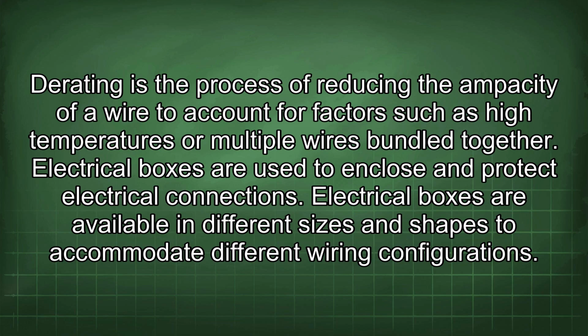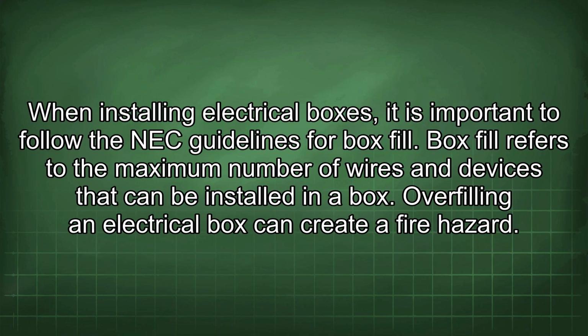Electrical boxes are available in different sizes and shapes to accommodate different wiring configurations. When installing electrical boxes, it is important to follow the NEC guidelines for box fill. Box fill refers to the maximum number of wires and devices that can be installed in a box. Overfilling an electrical box can create a fire hazard.